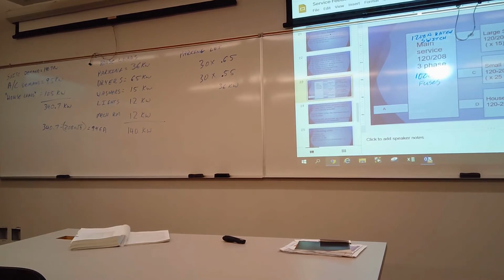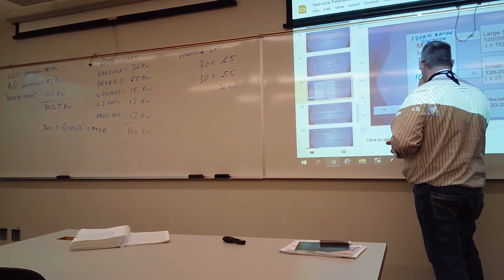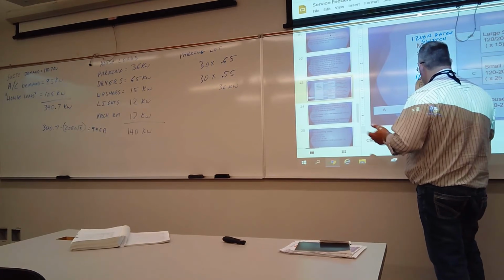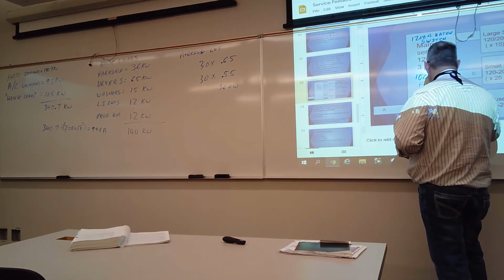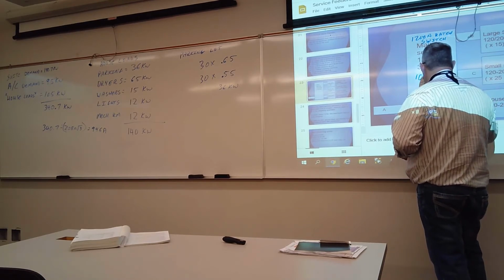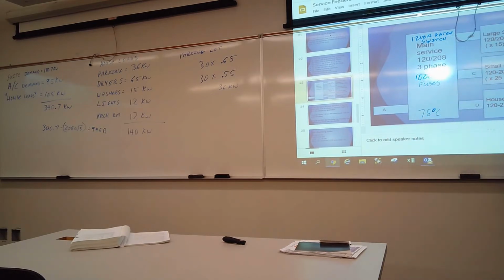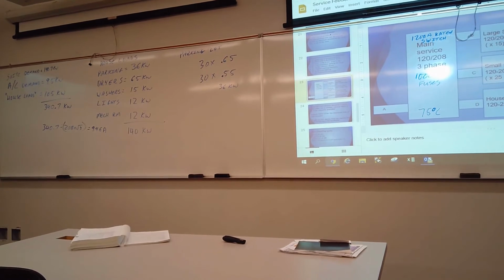Big conductors. So to save some money, let's use aluminum R90 conductors. Let's say all our termination temperature, we can spec that all equipment must have a termination temperature of 75 degrees Celsius or higher. Right, just put that in your spec for your design, and you'll be fine.